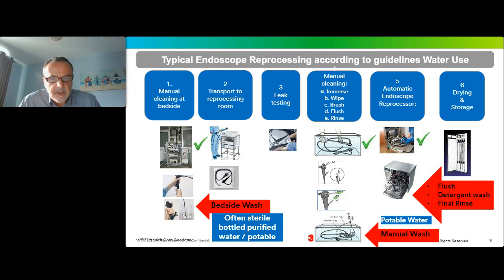But then, of course, a final rinse takes place to remove all of the debris and chemicals used during the earlier stages of the process. And the final rinse water is vitally important in maintaining the quality of the scope after it's removed from the washer disinfector and then put into storage, because that is the final step in the decontamination process. So if the scope gets recontaminated as a result of poor quality rinse water, then that contamination will simply sit in the scope until it's then reused.